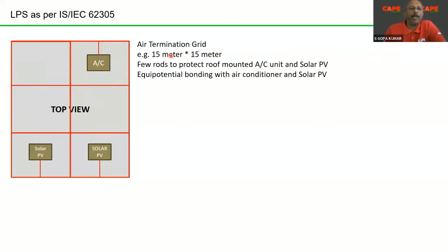For example, I made a grid of 15 by 15 meters, with a few rods to protect the roof mounted air conditioner and solar PV. Equipotential bonding with the air conditioner and solar PV has been made at the top of the building. This is a typical case. So a mesh, some rods, everything interconnected together. This makes the air termination system.